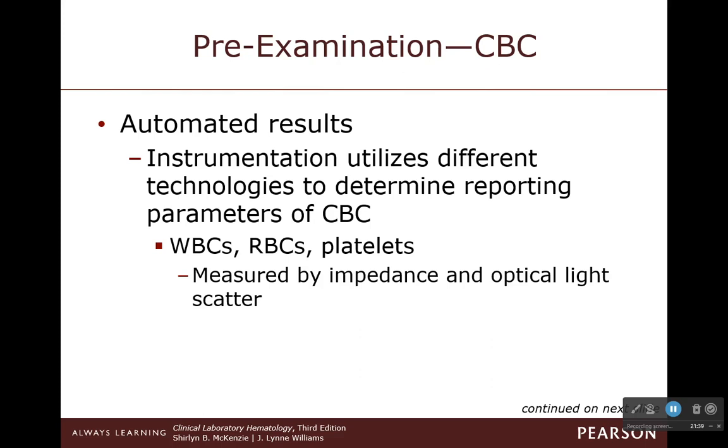They have an RBC chamber that is doing red blood cells that way. Then it has a WBC, platelet, and hemoglobin chamber, all right? And it's usually round, like a cup, okay? And it shoots the sample in, okay? But then it also has the same impedance as it goes through.